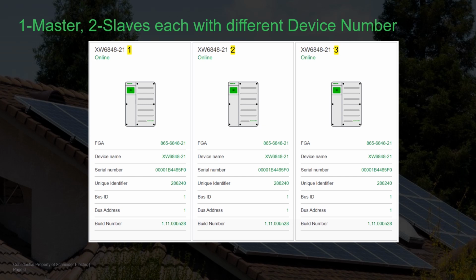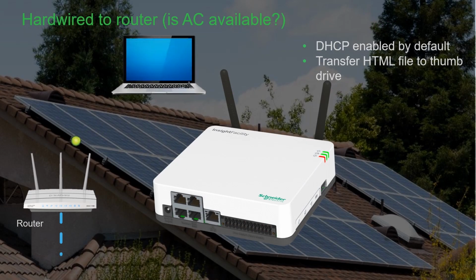Battery type and capacity must be set in each XW Pro unit unless you are using a compatible BMS. If a router is available at the site, you can plug an Ethernet cable from the Ethernet port of InsightHome or InsightFacility to the local area network port of the router, which in turn may communicate with your computer wirelessly if it has that capability, or you can hardwire your computer to the LAN port as well. Then simply plug a thumb drive into the USB port of InsightFacility for about 10 seconds. Then transfer the thumb drive to your laptop.